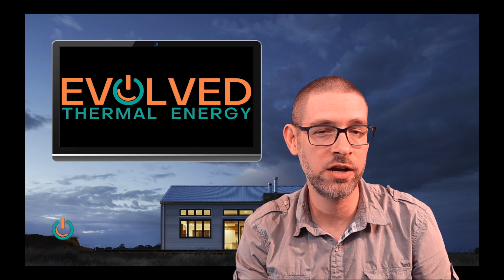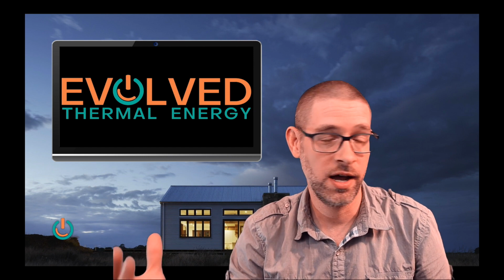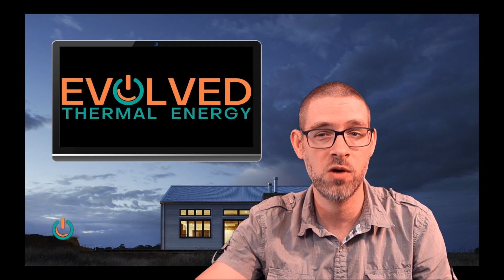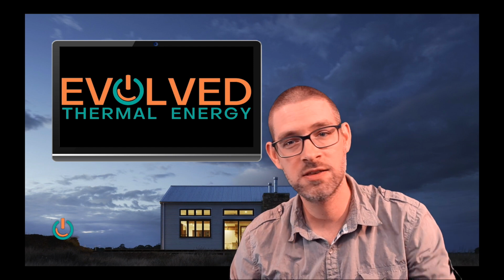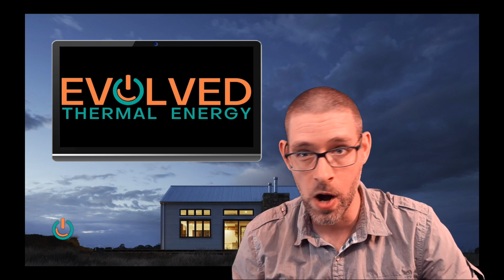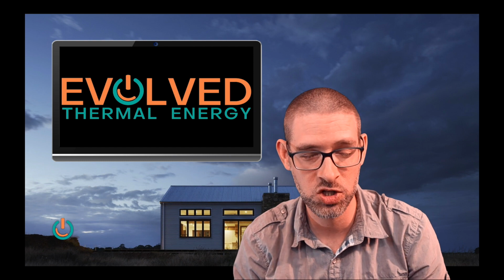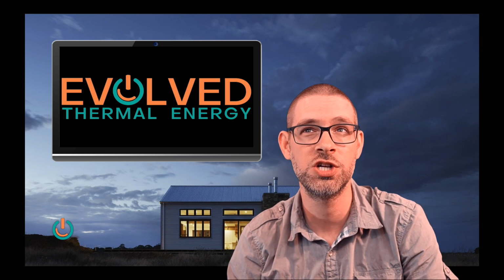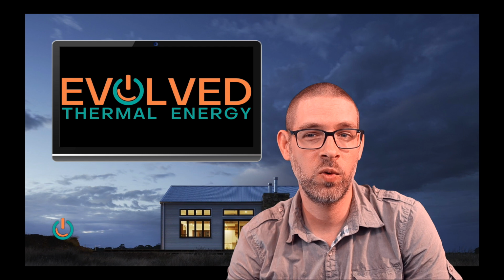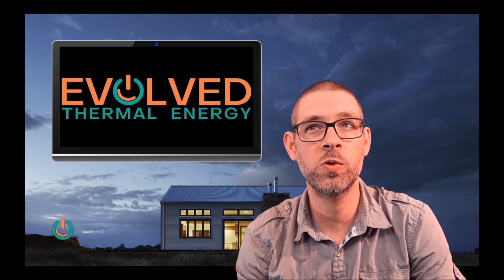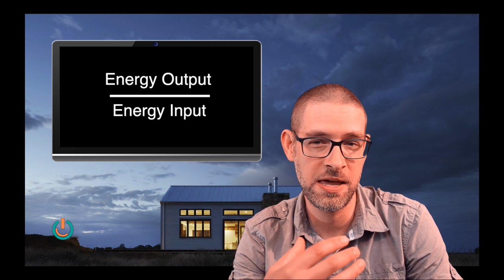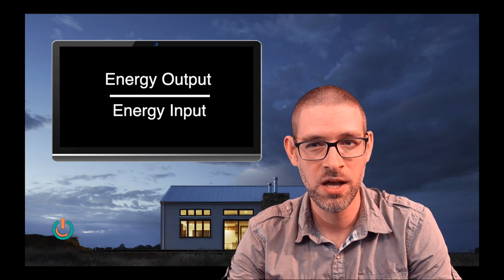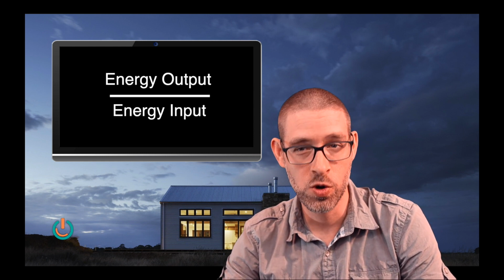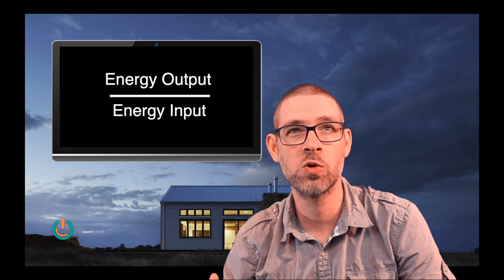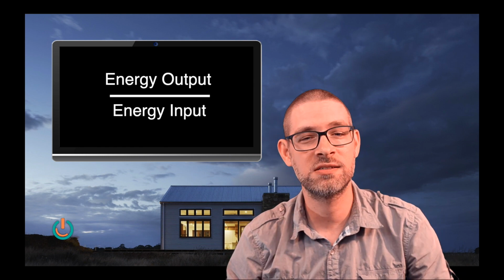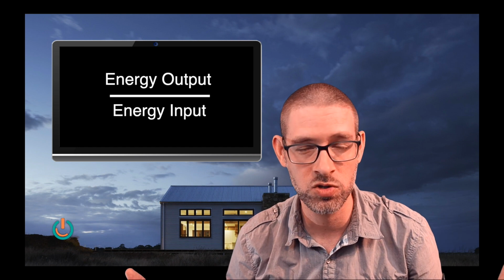Now, we use electrical energy to power the heat pump because a heat pump is essentially a refrigerator. So we have to power that refrigeration process and the small circulators that circulate the fluid around the pipe, the ground loop heat exchanger that's in the earth, to pick up that thermal energy. But we have great benefit from doing that. The electrical energy that we put into the system is far less than the thermal energy that we get out of the system. So the work energy we put into it must be less than the energy that we get out of it. Otherwise, there's no point in doing it.